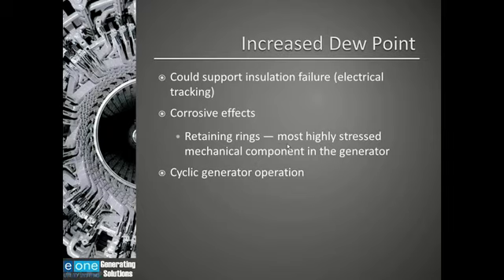With baseload generators, as I said, you have a constant warm temperature in there. However, with peaking units that are cycling, you have a chance for the temperature to fluctuate, and you also have a chance for condensation to form inside the generator. This picture is of a retaining ring failure. As I said, the retaining ring is the most highly stressed component in the generator, spinning in some cases at 3,600 RPM, on a nuclear unit 1,800, or if you're in Europe, 3,000 and 1,500.